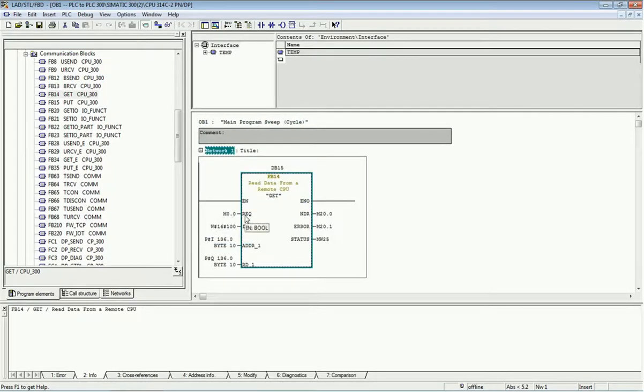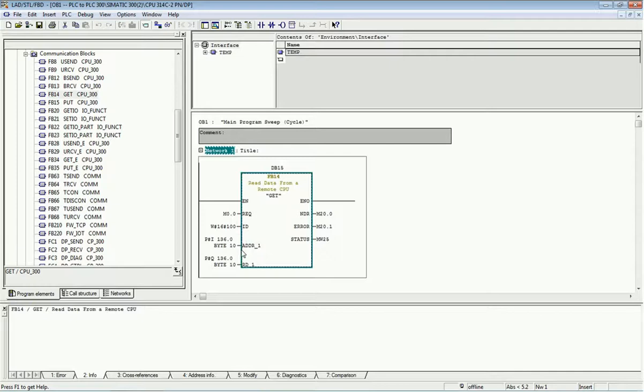The M0.0 is the request bit, continuously sending the clock pulse. The ID is the same as used in the PUT block — 100. For the addressing, I136.0 is the starting bit, and I want to store a total of 10 bytes of data in Q136.0. This is the opposite addressing to the PUT block. Here you will also get error and status codes, and you can assign any memory bit or memory word.